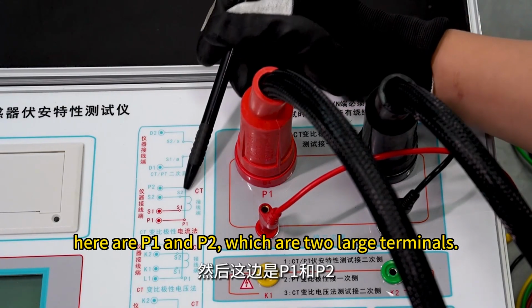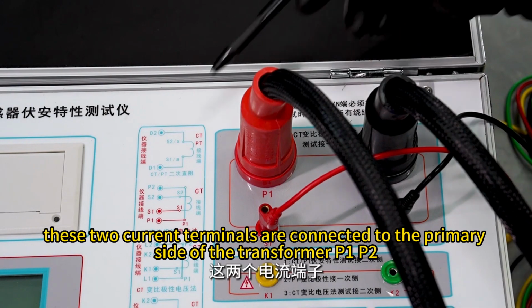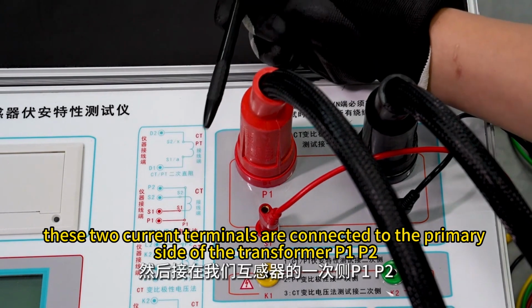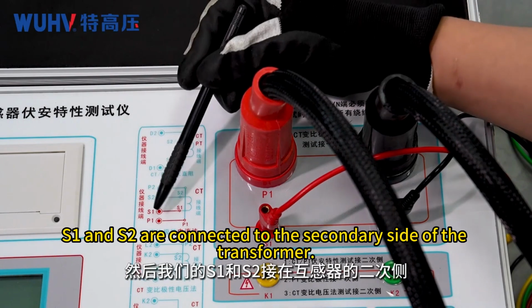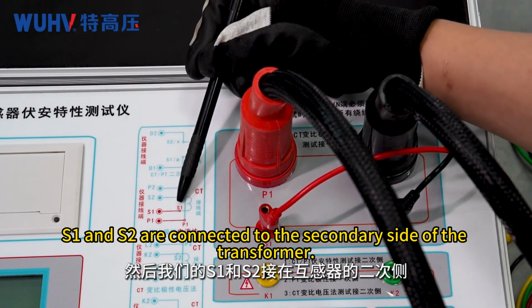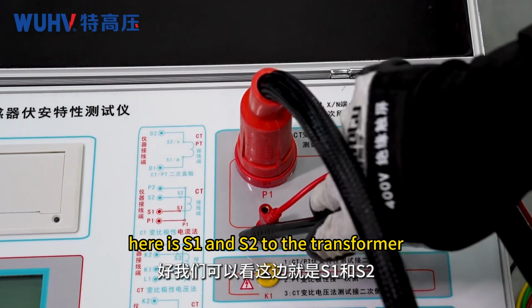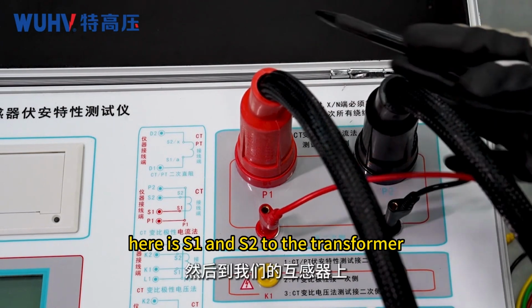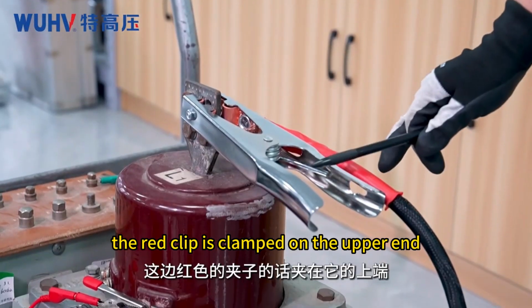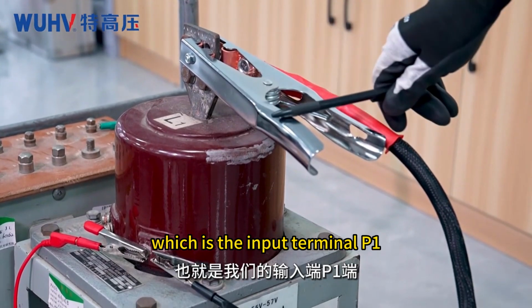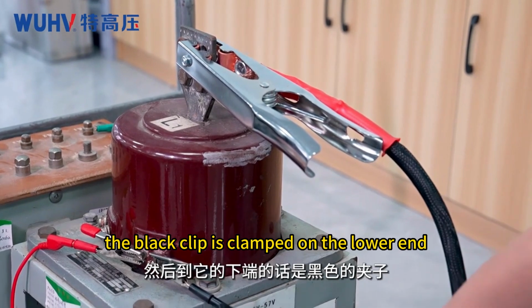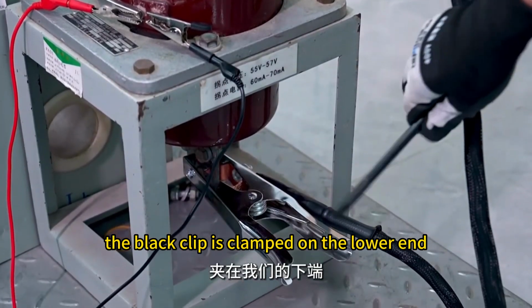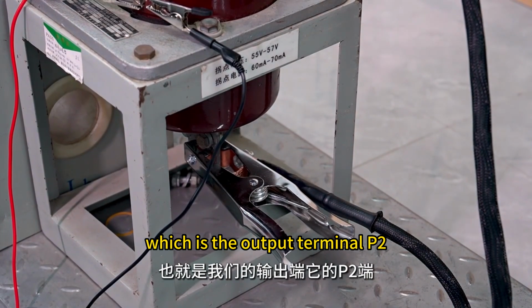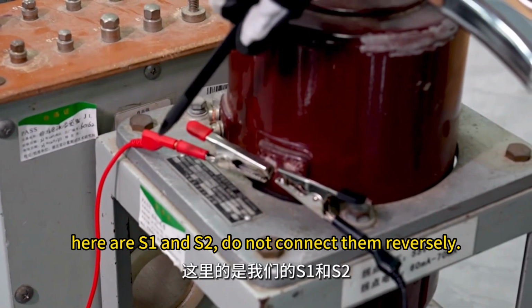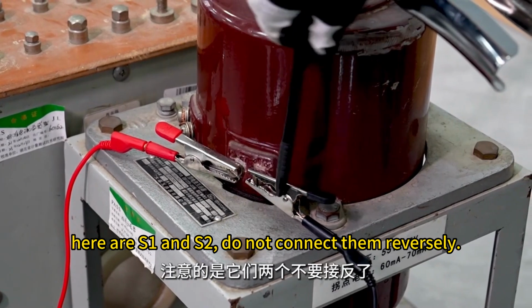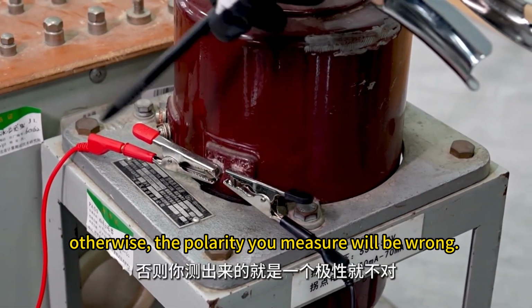Here are P1 and P2, which are two large terminals. These two current terminals are connected to the primary side of the transformer P1 P2. S1 and S2 are connected to the secondary side of the transformer. The red clip is clamped on the upper end, which is the input terminal P1. The black clip is clamped on the lower end, which is the output terminal P2. Here are S1 and S2, do not connect them reversely. Otherwise, the polarity you measure will be wrong.